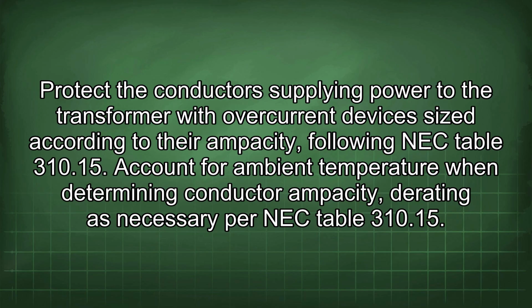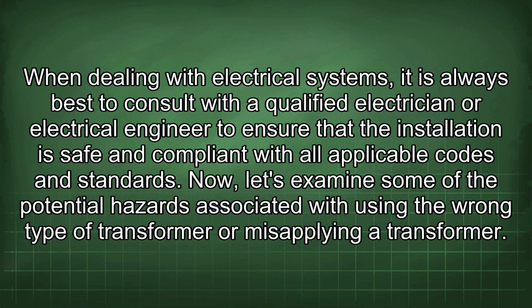Protect the conductors supplying power to the transformer with overcurrent devices sized according to their ampacity following NEC Table 310.15. Account for ambient temperature when determining conductor ampacity, derating as necessary per NEC Table 310.15. When dealing with electrical systems, it is always best to consult with a qualified electrician or electrical engineer to ensure that the installation is safe and compliant with all applicable codes and standards.